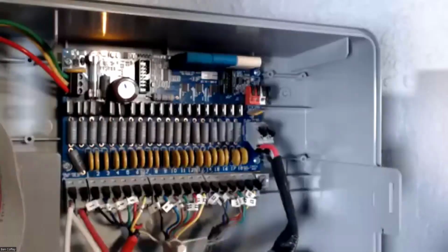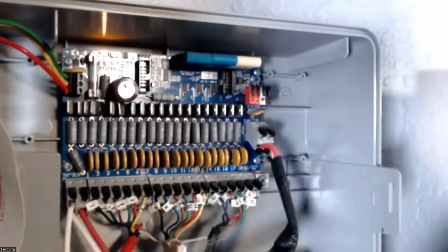So here we'll notice that we only have an orange light. This is already telling me I have that 24 volts coming in, so I don't have to probe with a voltmeter. So if you don't have that light, tell me what that means. That is when we want to then take out our voltmeter. Obviously we want to go for the lowest hanging fruit - is my fuse blown? If it is, replace it with the equivalent and then work your way back.